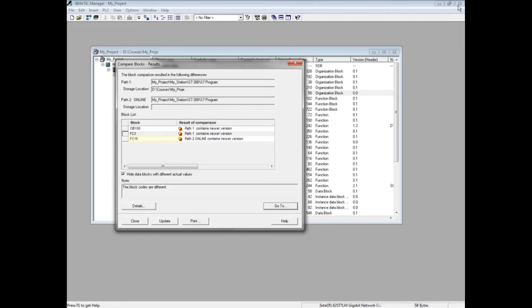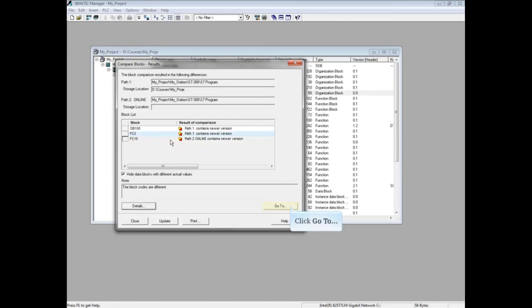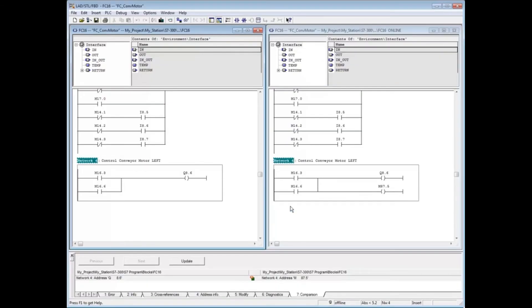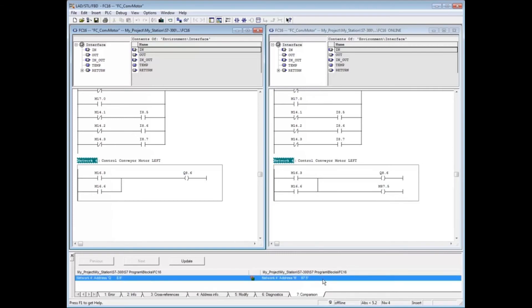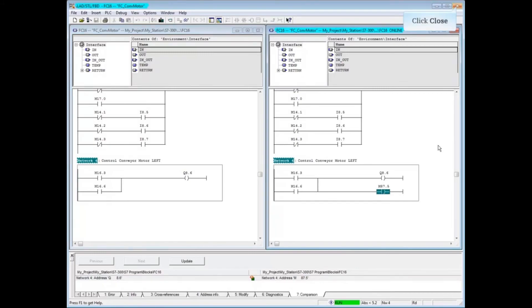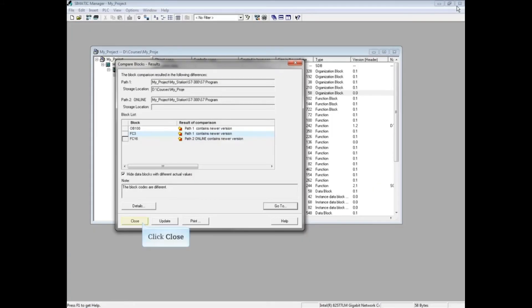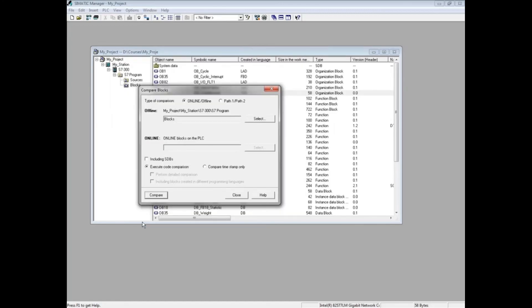FC16 in the comparison list shows that Path 2, the online path, has the newer version. Click the Go To button. In the comparison tab at the bottom of the programming editor, you can see that Network 4 in the online window has the added address M87.5. Close the programming editor and close the Compare Blocks results window.